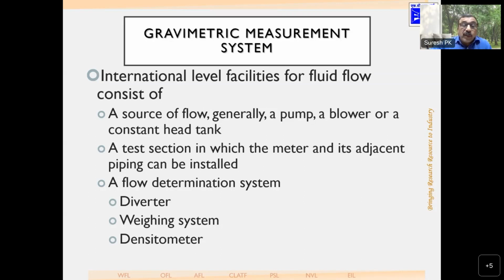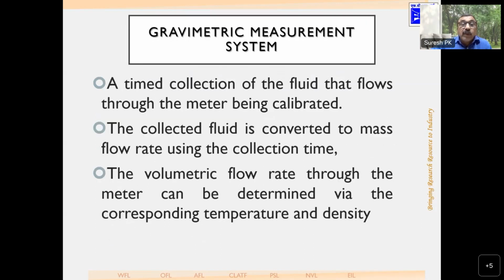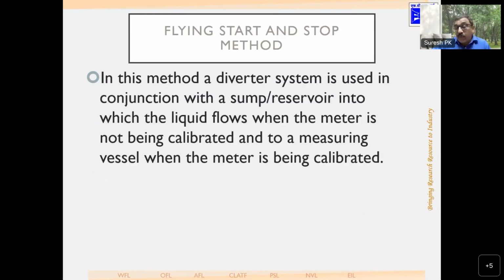The flow determination system consists of a diverter, weighing system, and a densitometer. Basically, it's a timed collection of the fluid that flows through the meter being calibrated. The collected fluid is converted to mass flow rate using the collection time. The volumetric flow rate through the meter can be determined via the corresponding temperature and density.